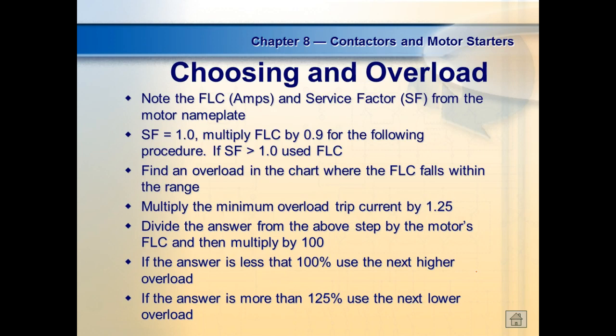Normally industrial motors have a service factor, because they understand that situations will occur where you accidentally overload the motor. So when they size those heaters, they assume the motor is going to have an overload of at least 1.15, I think is what it is. So that's the way the heaters are sized, for the current in that chart times the service factor. If I've got a service factor of one, I'm going to have to go to a lower size. So we only use 90% of the full load current, only if it has a service factor of one. If it's more than one, we just use the full load current. That makes sense now?